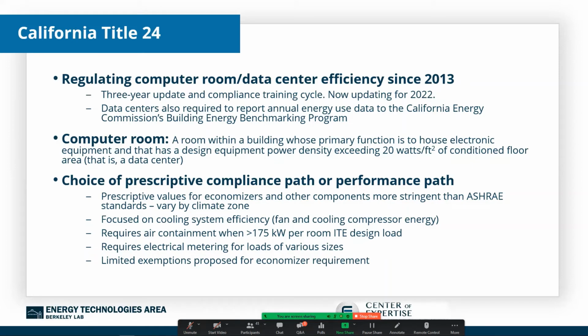The prescriptive path is very much focused on economizing, on cooling system efficiency, particularly fan and cooling compressor energy. Larger data centers, and not even really that large, anything with greater than 175 kW of design load, has to have air containment, so hot and cold aisles. There is required electrical metering to varying degrees depending on the load. And there are now some proposals for limited exemptions for economizers, say in jurisdictions where they discourage cooling towers.